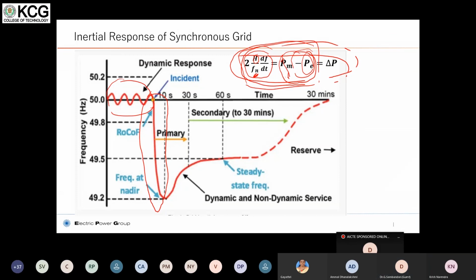Correct. You're right. But the issue is, the microgrid has to be connected to some generation, right? Yes. No microgrid today operates without synchronous generation. For example, where do you provide your microgrid power? It has to be provided to households, domestic, irrigation. All these loads still have motors and other rotational masses. Still, you need some inertial support. So it cannot be totally independent.